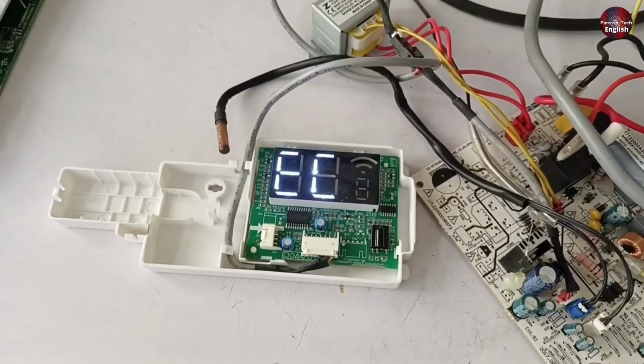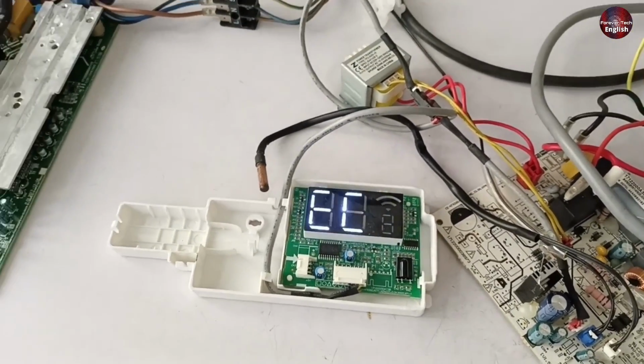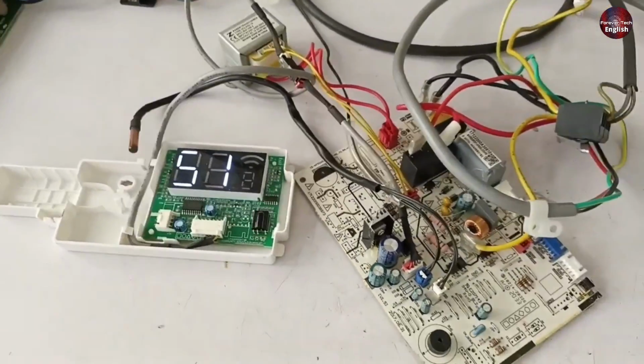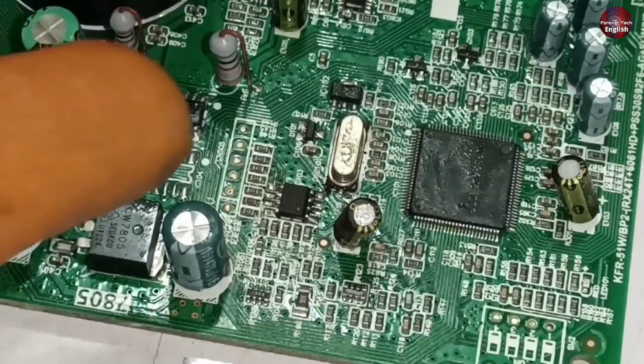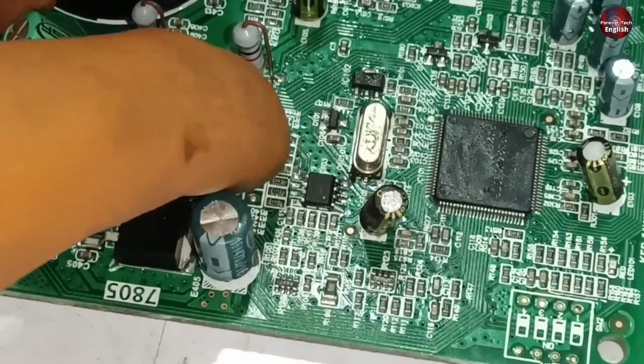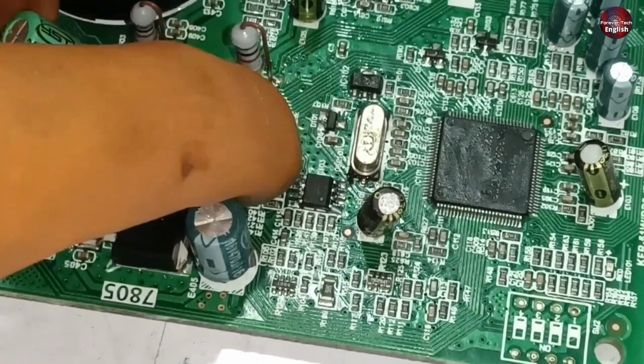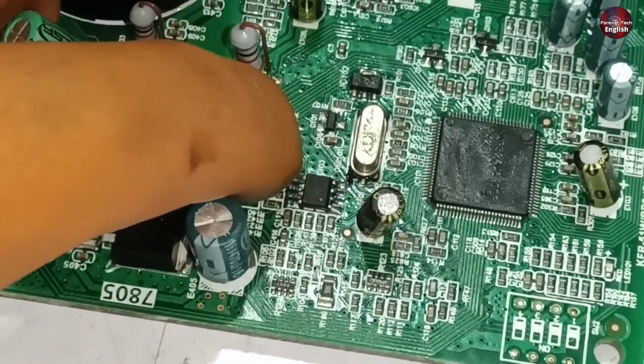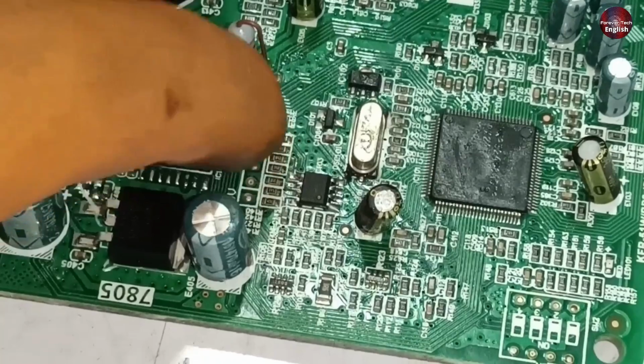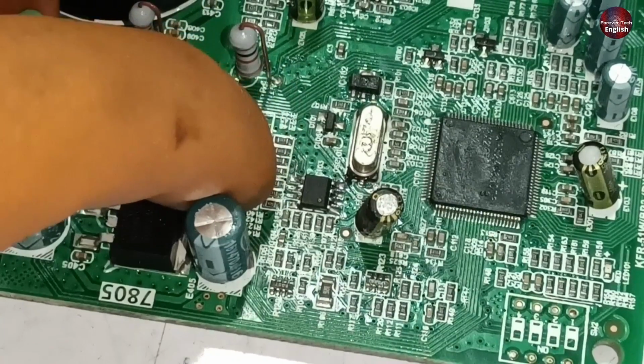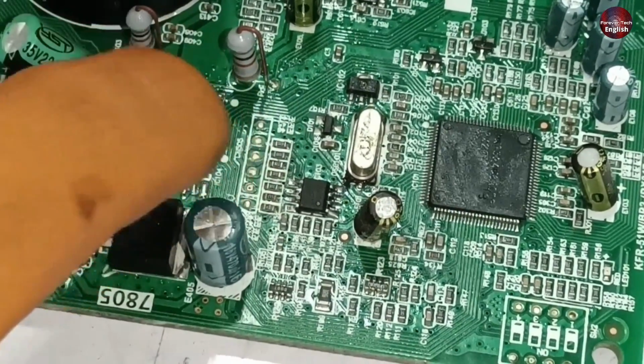Now, the display is showing an EC51 error code. This error is not of the indoor circuit but of the outdoor circuit board. When this EEPROM of the outdoor unit gets corrupted or short-circuited, then this error will be displayed on the display. I will check the operating voltages on this IC. If the operating voltages are missing, then it means that something else in the circuit board is faulty.